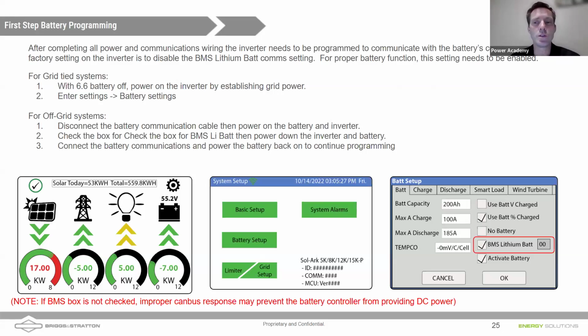The reason you might need to do that is that the inverter is not going to be sending the correct signals to the batteries until we get this box in the bottom right-hand corner. If you go into settings and then battery setup, the battery is looking for this BMS lithium battery box to be checked. Until that box is checked and you click OK, it won't be sending the appropriate signals to the battery. So it could even keep the battery from coming alive if the inverter is not set up properly.